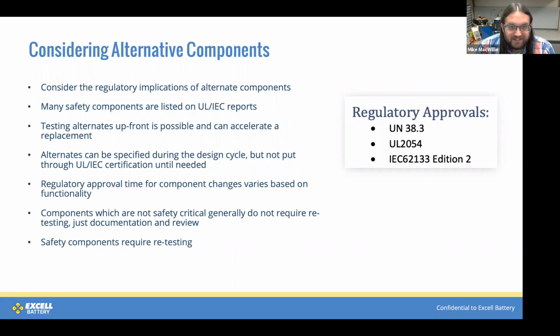Another option, if it's less risky, is to specify those alternates during the design cycle, but not put them through regulatory certification until they're needed. This saves you some of the upfront costs at the expense of response time if you need to switch a component. So if you do need to switch a component, the regulatory approval time for those components varies based entirely on how they function within the BMS.